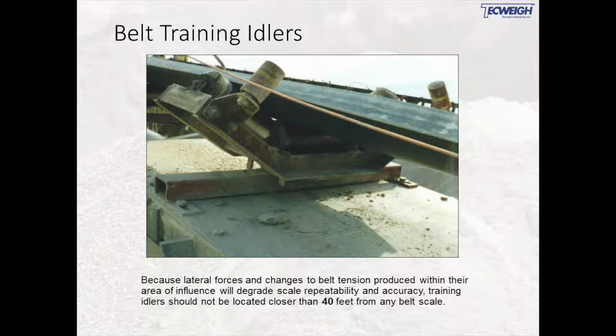Be careful about installing a scale close to a training idler, or sometimes you might have a scale working properly, then someone installs a training idler close to the scale. It will cause repeatability issues. Ideally, don't put a training idler within 40 feet of a belt scale.